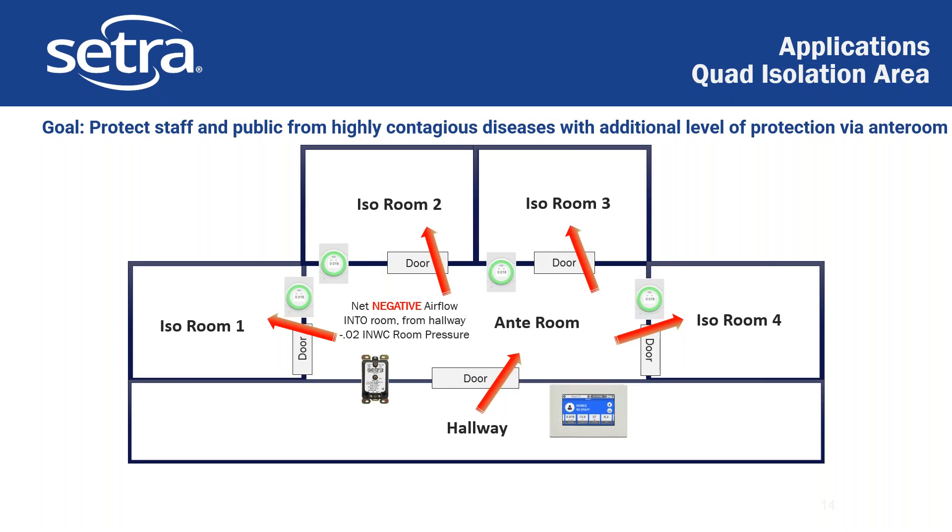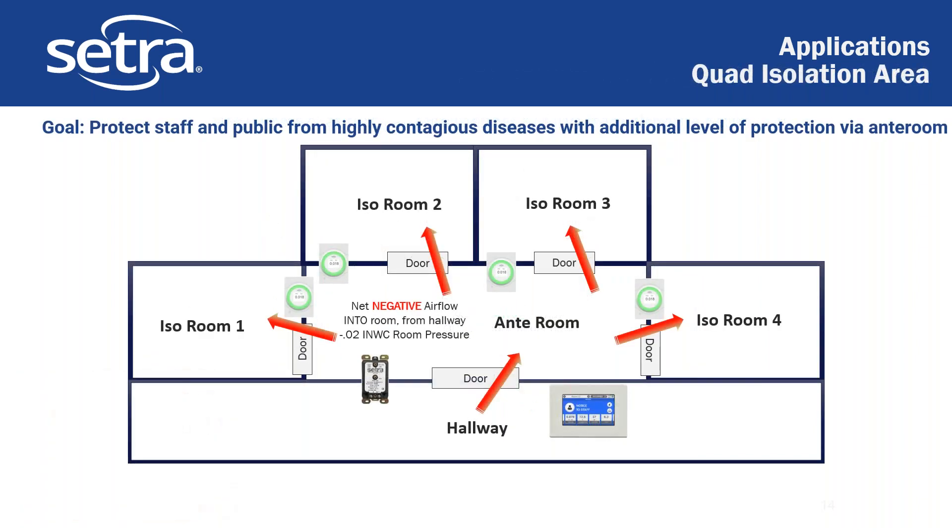This is a more advanced solution where we also have an anteroom. What's important to note is your anteroom has to be at least 0.01 inches of water column negative to the corridor, and then each of the rooms has to be 0.01 to the anteroom. We're showing 0.02 here, but the actual requirement is 0.01 — though 0.02 is a common level to maintain. In this case we're using four Setra Light products and a standard Setra 264 pressure transducer reporting into a SetraFlex monitor that displays all the data from all those monitors outside the room.